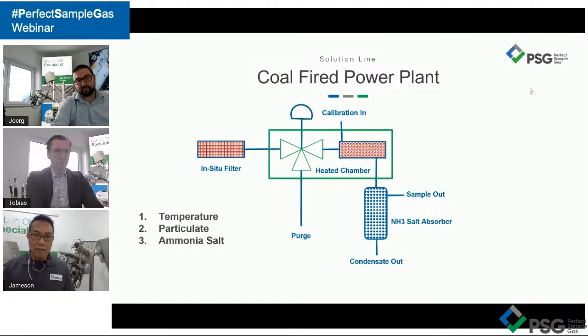I mentioned again, it is not the ammonia, it is when there is a slip. If there is a slip after the SCR process, and you happen to do a back purge, you get a clog at the filter almost immediately. So a large filter element can play a very vital role. Why a vital role? In any event, if there's any mistake, you just simply remove the filter, a very economical ceramic filter, and replace it without removing the probe, without taking out the flanges, just remove the filter element.